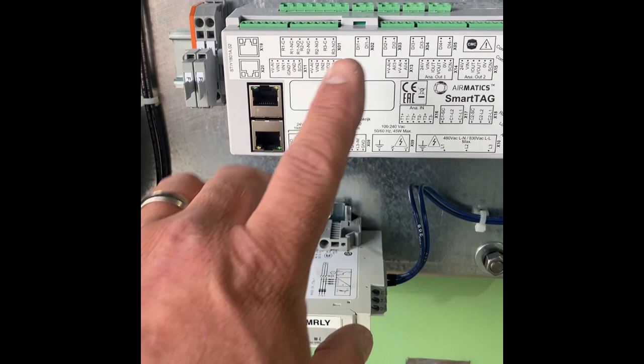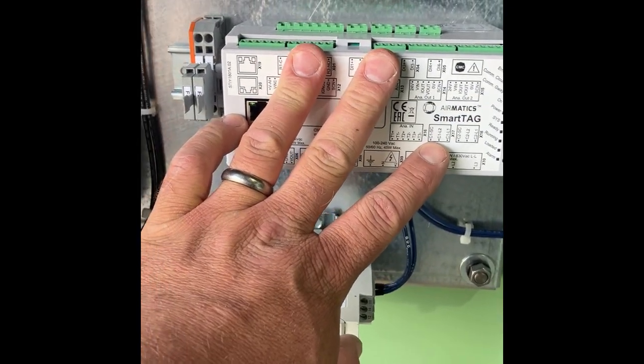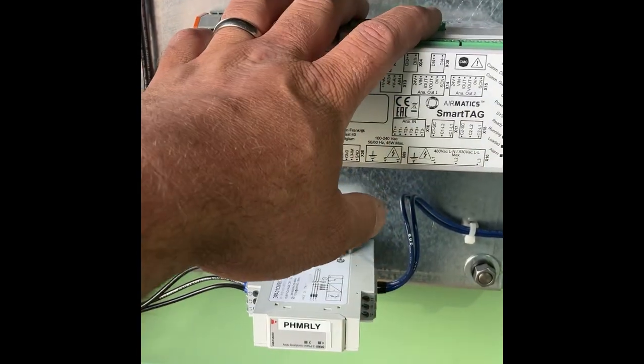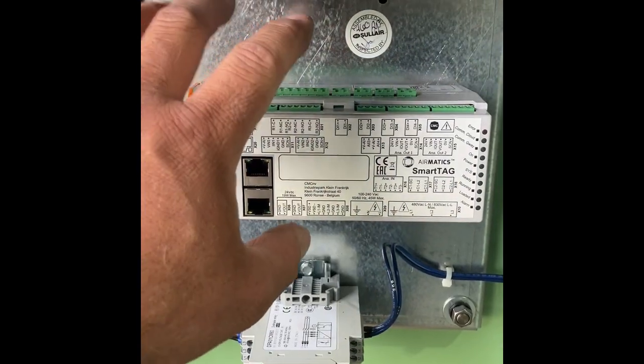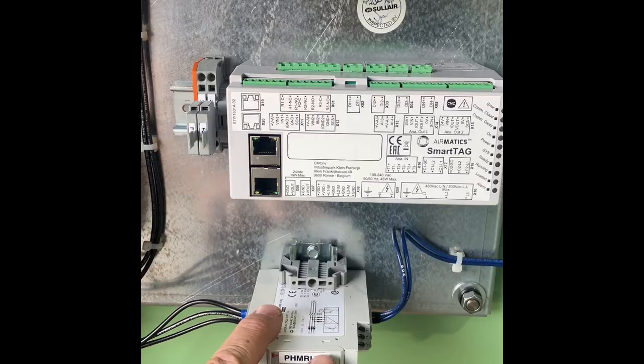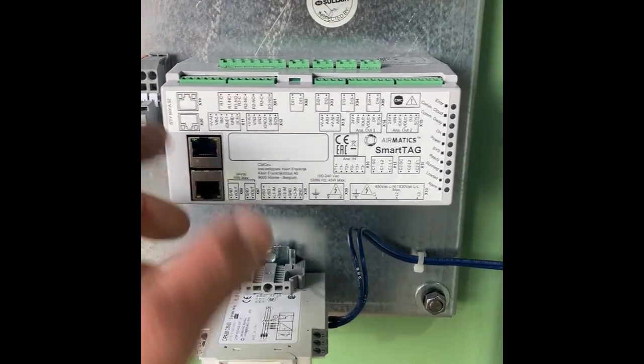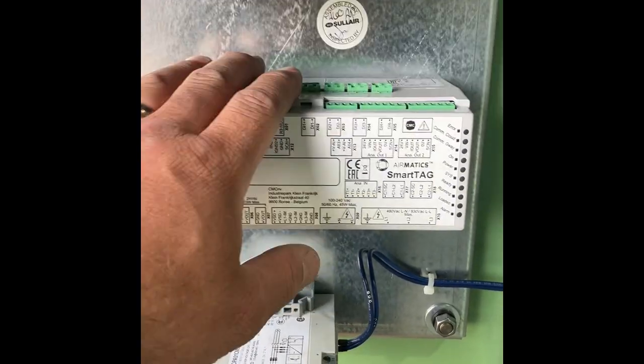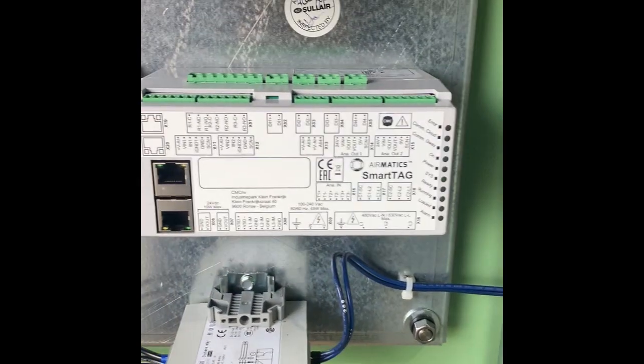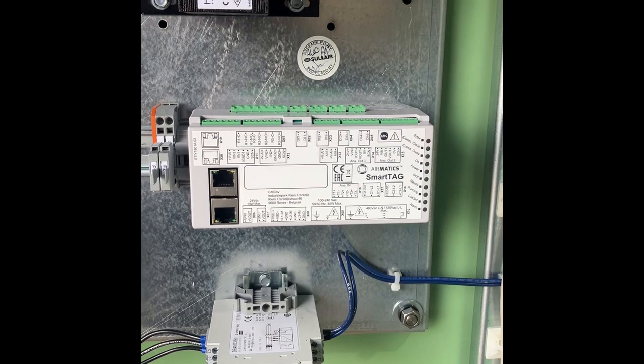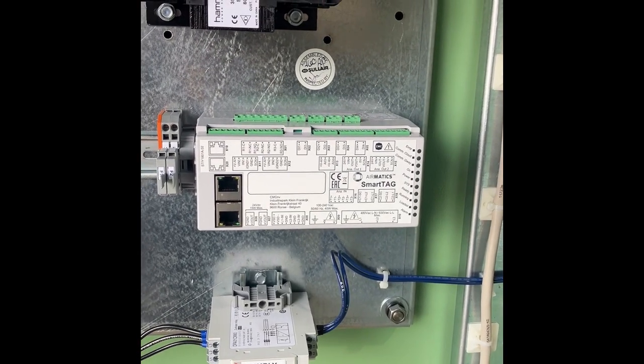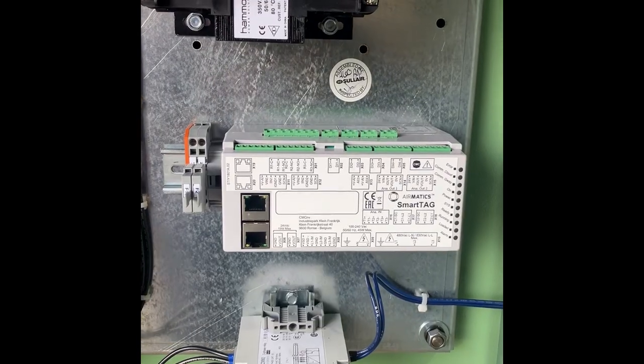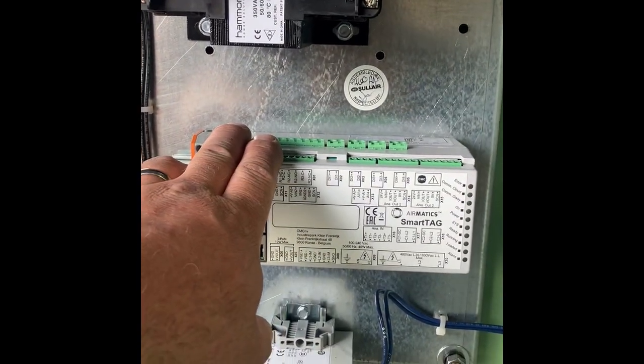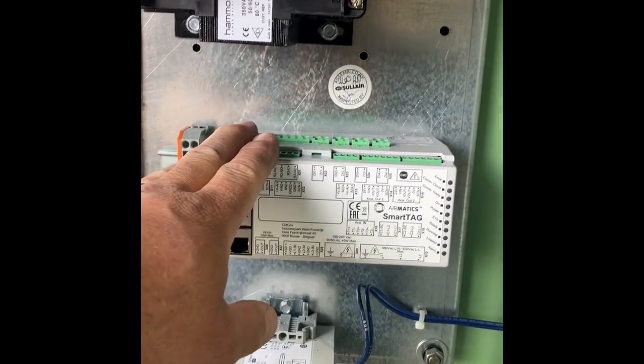Just another quick note: anytime you make a change inside a compressor electrical cabinet, whether you're adding hardware or whatever, you always need to take into account the necessity of these items to dissipate heat. That's why you don't want to put two items that generate heat or need to dissipate heat right next to each other. You want to leave some space so they can breathe. That's actually a UL standard. Anybody who's UL certified for panel building will tell you there are standards they have to follow when they build these panels to allow for heat dissipation.